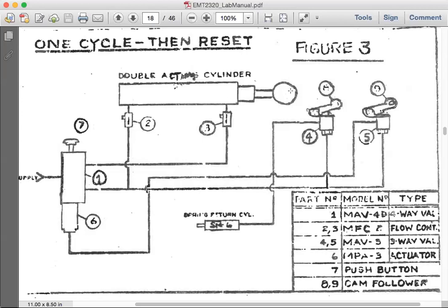But when the piston returns, the flow control controls how quickly the pressure vents out from the left chamber. Therefore, number 2 controls the speed of the double acting piston returning, by controlling how quickly the left chamber is venting out in order for the piston to return.